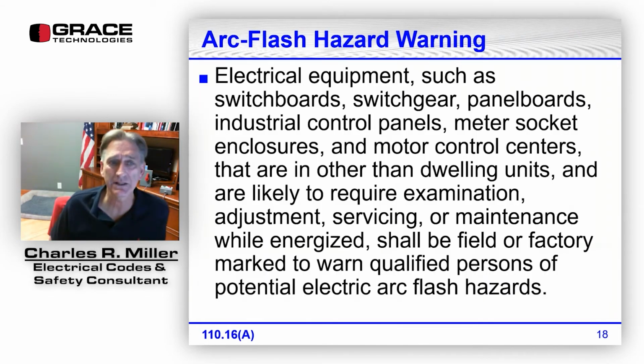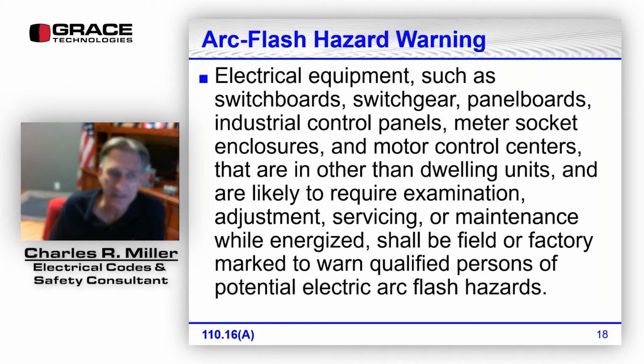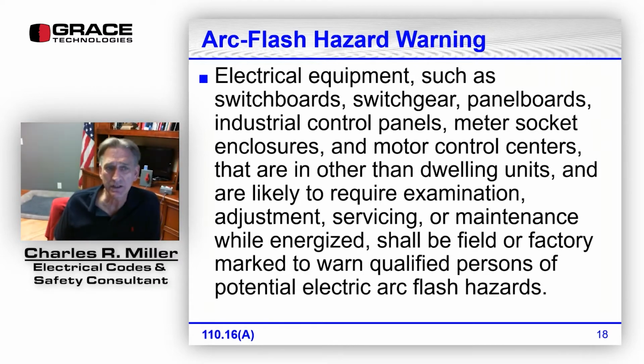Arc flash hazard warning labels. These have been in the National Electrical Code for a while. For the most part, for a number of editions, it was just a generic label. We'll get to that on the next slide. What has to be labeled?